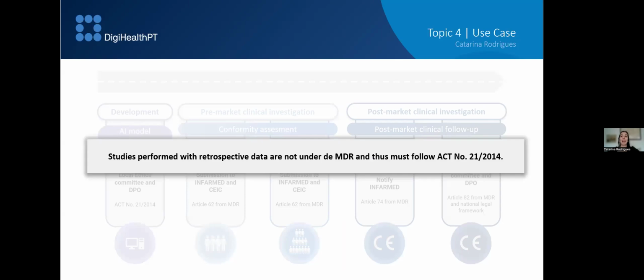So, there are some situations in which you can perform the studies only with retrospective data. And in that case, the study will not be under the MDR, and thus it must follow the national law for clinical investigation. This means that if you are using retrospective data in your studies, you will be submitting your study locally to the local entities.